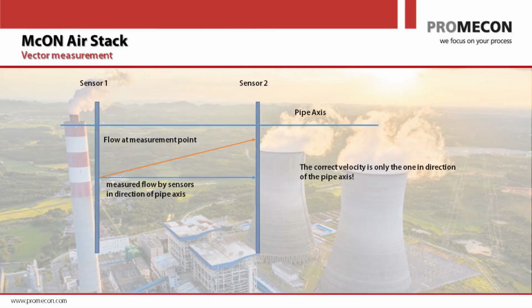But I promised you something more. I also promised you to talk about swirl and why, for us, it doesn't matter whether we measure velocity or we measure the mass of the air. It's the same thing. Look at this picture here. You can see that the two sensors are mounted perpendicular to the axis of the duct. And that means that the distance between the sensors is parallel to the duct. And the distance is important because I mentioned delta P and delta temperature measurements are all measuring only scalar values. Now you might say, well, time shift is also a scalar value. There's no direction in time. That is correct, but we measure distance over time.